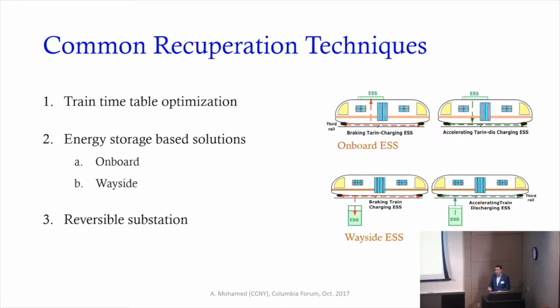The third method is a reversible substation. Typically the substation, or rectifier substation, gets power from the main grid through rectifiers and feeds your third rail, the DC rail that supplies the trains. This is typically an uncontrolled rectifier, which means it is unidirectional - it gets energy from the main grid to the subway system, but not the opposite. So you could replace this rectifier with a bidirectional converter, or leave it as is and add another inverter in parallel, enabling energy to go back to the main grid.